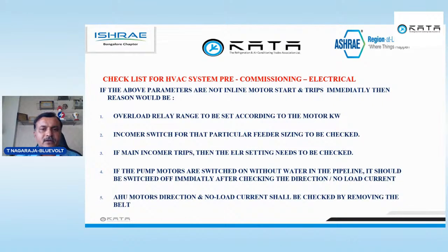Above parameters are not in line. It starts and trips immediately. Then the reason would be: suppose you have started the motor, everything you checked, megger is okay, cable is also okay, motor is also okay. Then you start it, and the motor will run 1 or 2 rounds, then it will stop. Then it may be the overload relay range that needs to be set.